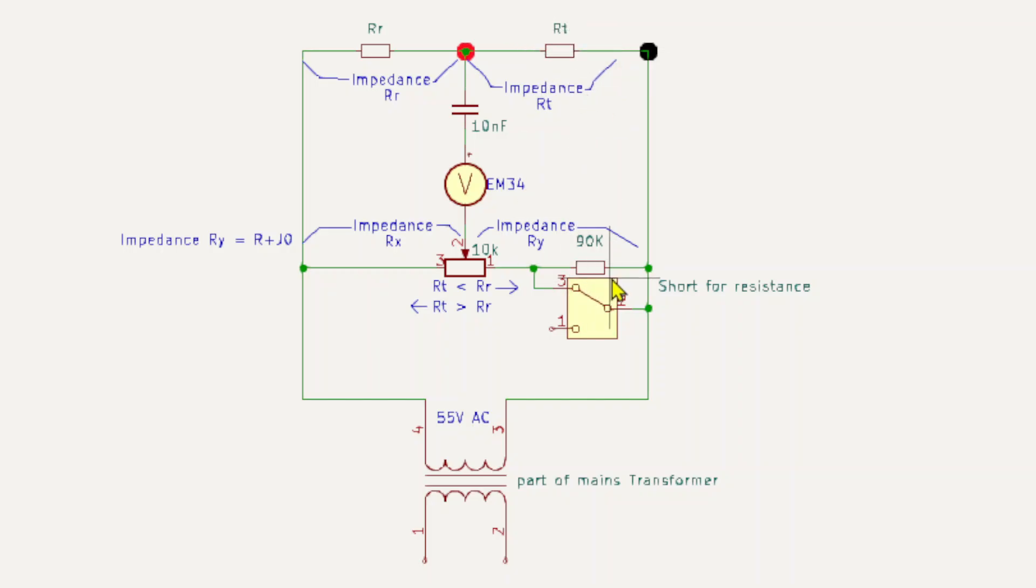So if we look closely, the 90k is shorted out by this switch for all the resistance ranges. It's bypassed by the switch. So the bridge is said to be in balance or nulled when the ratio of RR and RT is equal to the ratio of RX and RY.